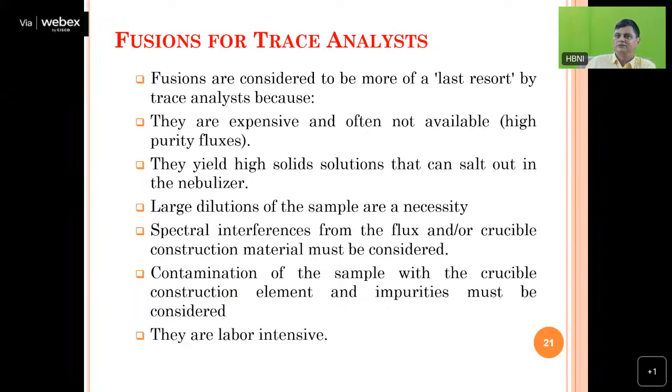They also yield high solid solutions, because most of the time the sample is analyzed using ICP-OES or ICP-MS. Once you have a high solid concentration, meaning the salt content is very high in your samples, it chokes the nebulizers. Of course, there are special nebulizers, Mira Mist nebulizers, meant for solutions having a high solid content. But generally we avoid it, and only when necessary do we do the fusion. And then larger dilution of the sample is necessary.